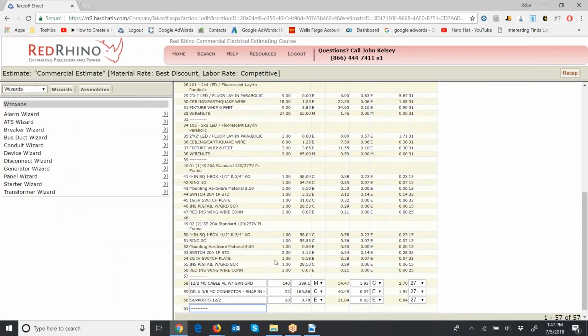Notice this, see how the program shows 12/2 MC cable with green ground? We input 140 feet, and it shows the price per M here, like I told you. Conduit and wire and MC cable is priced per 1,000 feet. That's what that Roman numeral M means, okay?